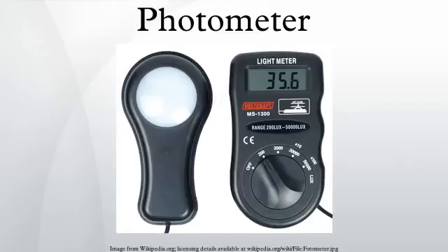Absorption photometers for work in aqueous solution work in the ultraviolet and visible ranges, from wavelength around 240 nanometers up to 750 nanometers. The principle of spectrophotometers and filter photometers is that monochromatic light is allowed to pass through a container with optically flat windows containing the solution. It then reaches a light detector, that measures the intensity of the light compared to the intensity after passing through an identical cell with the same solvent but without the colored substance.